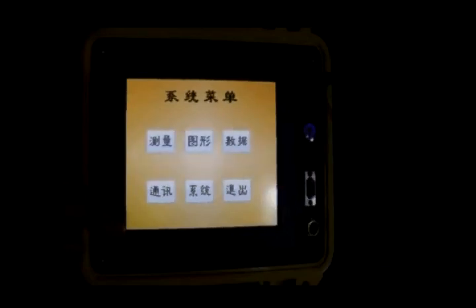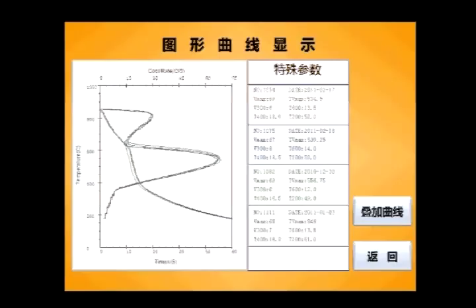Check the experiment curve and 6 other feature data. Operate the LCD touch screen as follows. You can check the experiment curve and 6 other feature data saved in a number. First, click the Graph button in the System Menu window, enter the Display Curve Parameter selection window, and touch the Channel Number button. Then, wait for the channels to be shown on the screen completely, and touch the number you want to check. Select Acting Graphic Grid, Graph, Characteristic Curve or not. Y means yes, and N the opposite. If you want to check superposed data, touch the Superpose button beside the curve, and select the number you want to superpose.